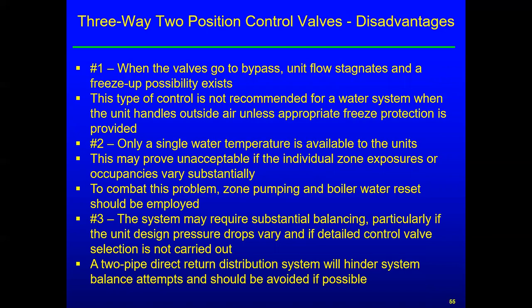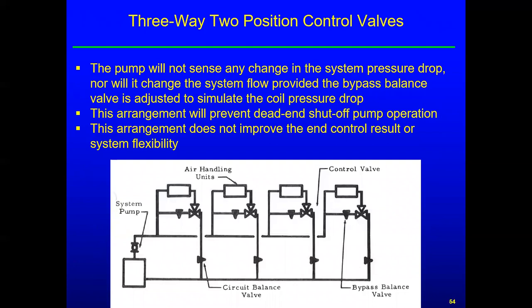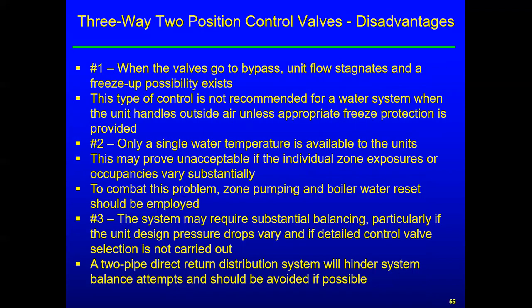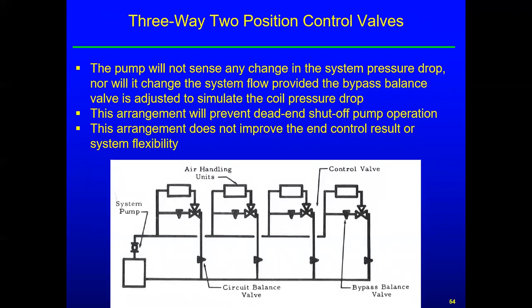Number three, the system may require substantial balancing, particularly if unit design pressure drops vary. So again, we may have balancing issues. A two-pipe direct return distribution system will hinder system balance and should be avoided. So by two-pipe, it means that I have to use the same pipes for heating or cooling. So in the summertime, I simply pump chill water through that piping system, and in the wintertime, I pump hot water. A four-pipe system would have separate pipes for hot water and chill water and two separate coils in each unit. So a comment on two-pipe direct return, which is what I'm showing right here.